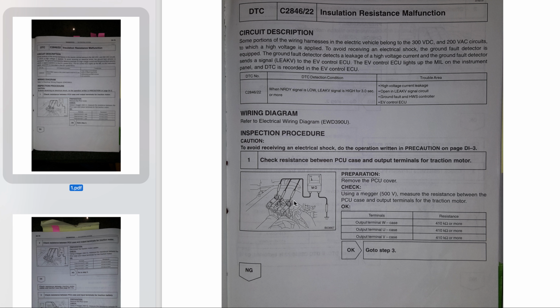The first thing it has you do is check the insulation resistance from the motor output terminals to the case of the PCU. The resistance of each of these cables should be more than 410 kiloohms. In my case, when I checked this, it was not. It was less than 100 kiloohms. So that means it's no good, and you move on to the next step, I think.